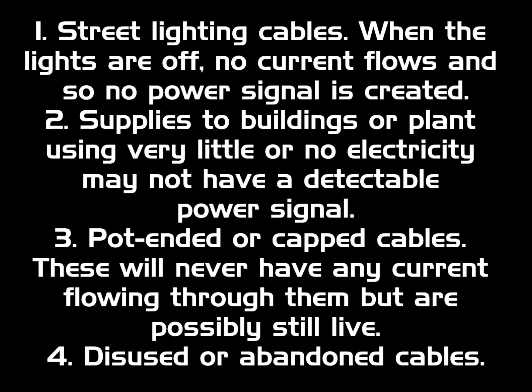1. Street lighting cables: when the lights are off, no current flows and so no power signal is created. 2. Supplies to buildings or plant using very little or no electricity may not have a detectable power signal. 3. Pot ended or capped cables: these will never have any current flowing through them but are possibly still live.